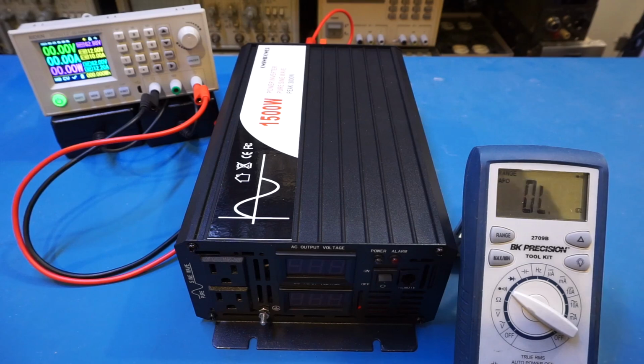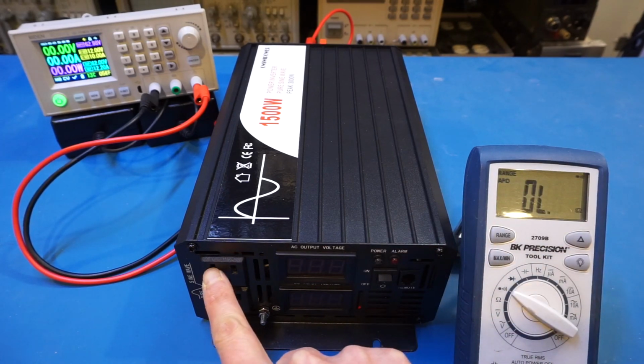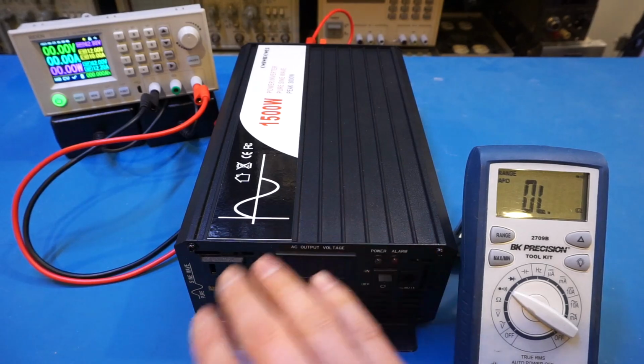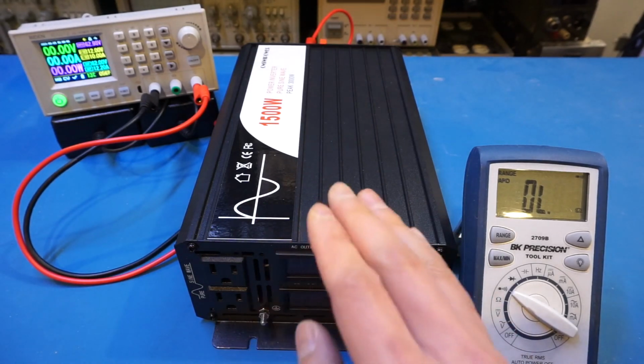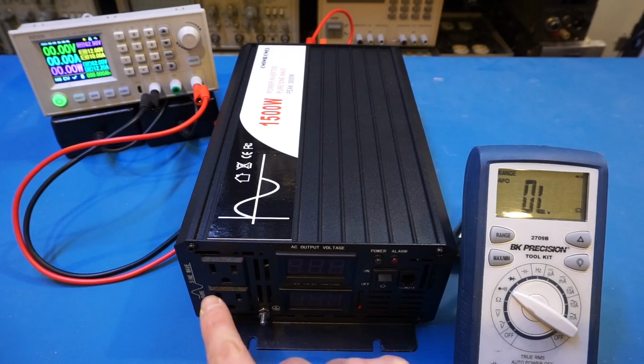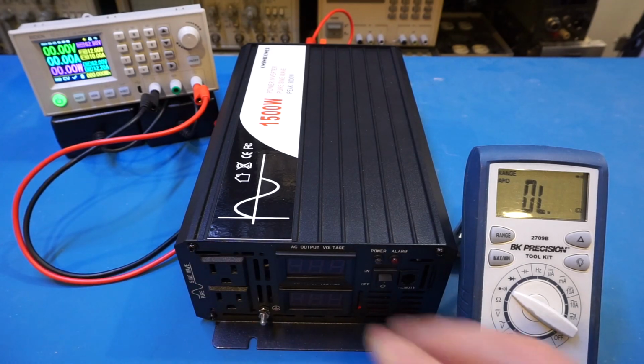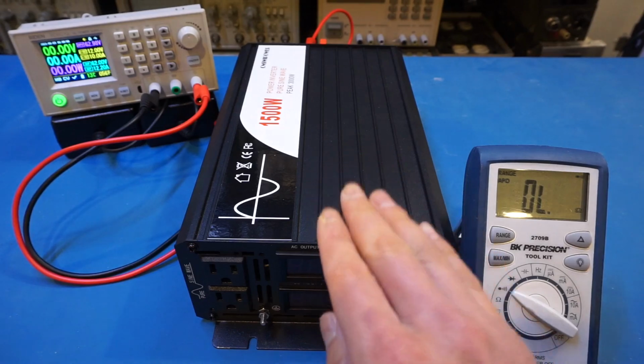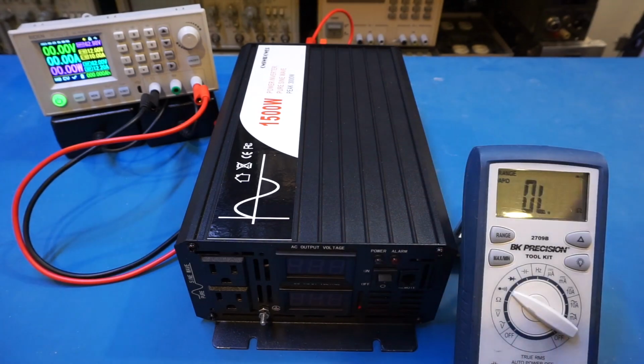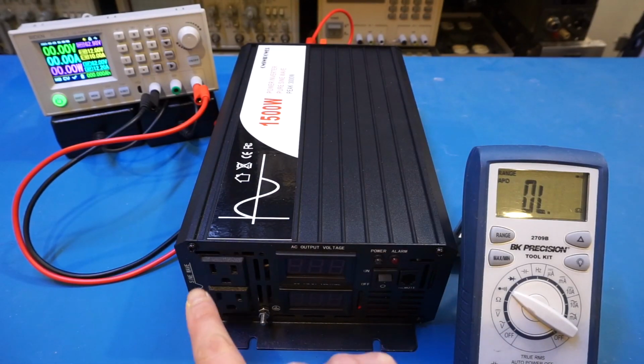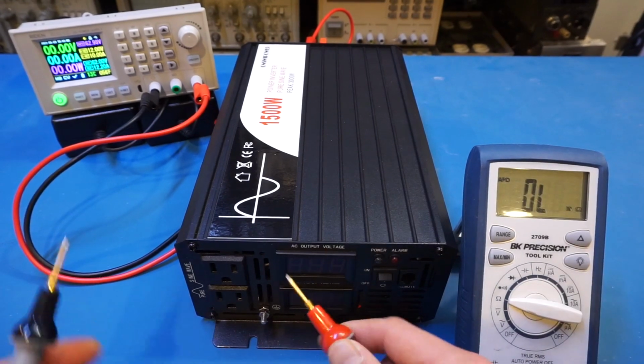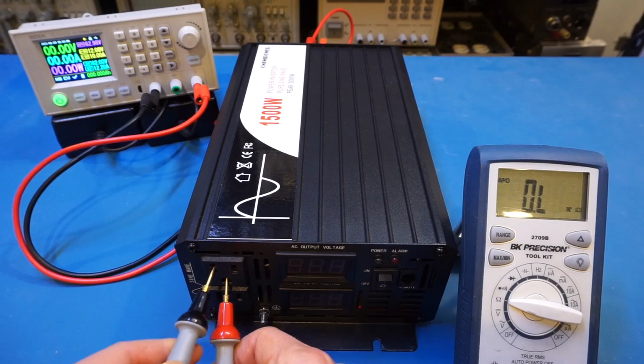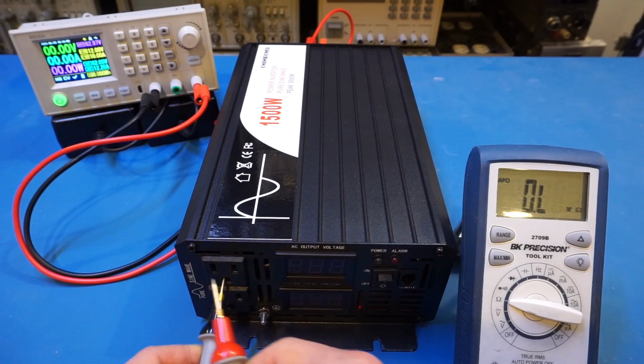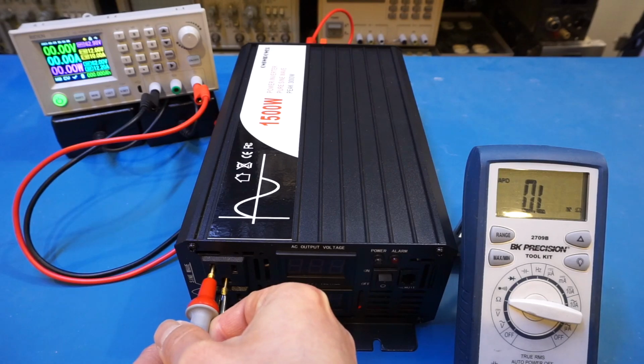Keep in mind that some inverters have the neutral pin carrying an output voltage, sometimes 60 volts, so you can't tie the earth pin and neutral pin together. But if you install your inverter to a transfer switch, that's almost always on the other end of the circuitry, where earth and neutral are tied together. For this one, let's check if there's any measurable resistance between these two pins, and it doesn't seem like there is.